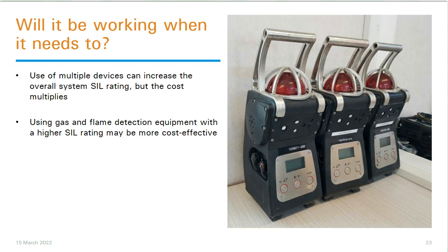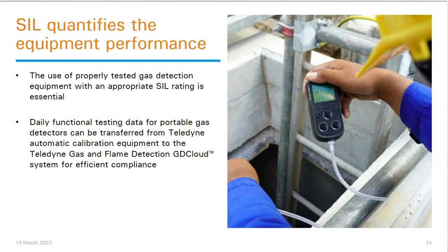And covering what we've just been saying there, the SIL rating of that portable or area gas detection equipment is really quantifying the performance of that equipment, and we've been using some of the appropriate terminology earlier on, the probability of failures on demand, or the percentage of time that it's available to give you the information that you need to operate a safety function, for example, to sound an alarm.